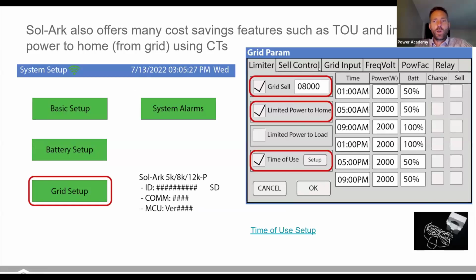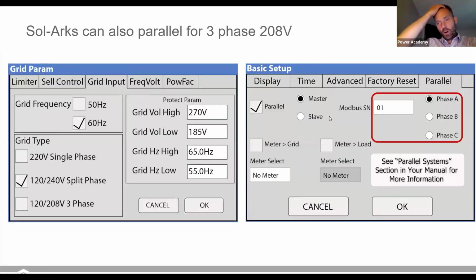Under the grid setup, you've got a lot of control here. You're able to limit how much power you overall sell back to the grid. You can also limit how much power you pull from the grid. So if your loads are, say, 10 kilowatts, but you've set this limit to only 2,000 watts, then that other 8 kilowatts you'd pull out of the batteries or pull out of the solar. You can also do time of use setup so that you discharge the batteries at a certain percentage as long as they're above that percentage during time of use. There are trainings on this, so I'm going to skip through it.